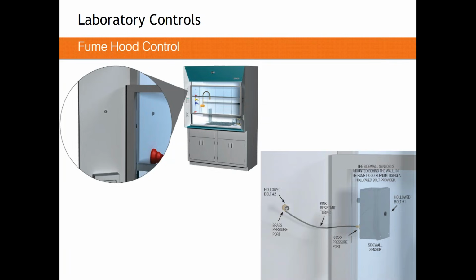For horizontal hoods and combination hoods, however, that open area is not only affected by the vertical movement of the sash. Specifically for combination hoods, the panes of glass can move to the left and right as well. So your sash may not be engaged, but you can open up a large amount of the open area using the horizontal sash panes. To measure and control these, what we use is a sidewall sensor. This is essentially a pressure sensor that measures the velocity through that threshold.